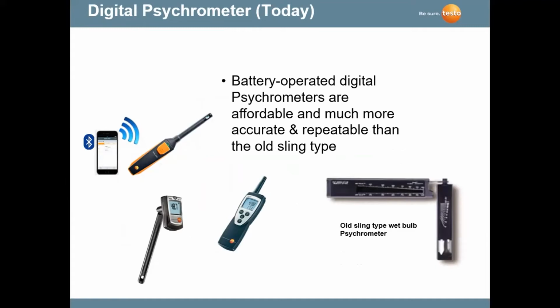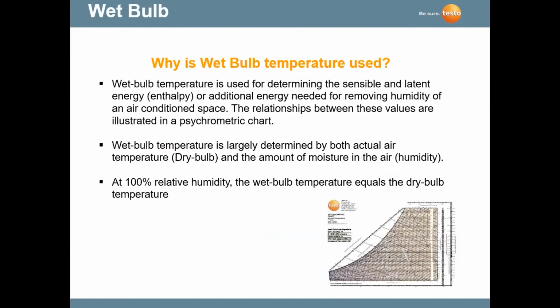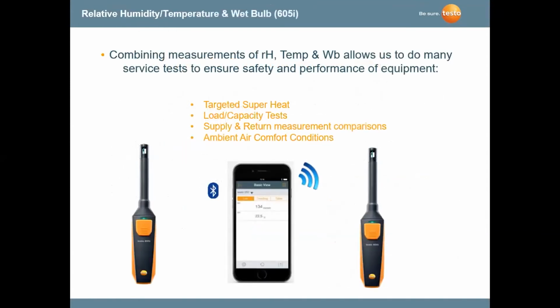But today we're using temperature measurement instruments. Most relative humidity sensors today have a temperature sensor as part of the specific relative humidity sensor. We're calculating the wet bulb reading from a sling psychrometer chart. Obviously, digital gauges have chips in them, and they're doing the calculations for you automatically. A very important measurement is the temperature reading, the relative humidity reading, and the wet bulb reading.